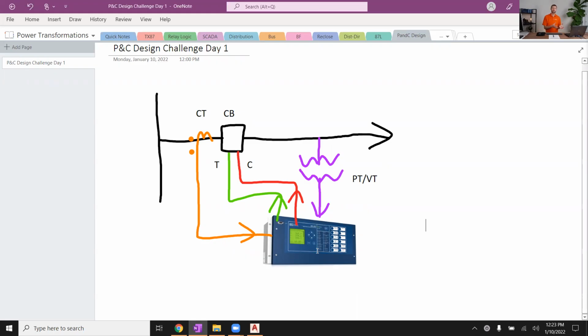Essentially, it's a computer. Nowadays, it's a microprocessor machine, and it's monitoring the power system from the voltages and or current signals and other input signals to detect anomalies, abnormal conditions, faults. And once it determines that a fault exists, it's going to take an action to automatically drive a response to clear that fault, to isolate the faulted section of the power system. That relay is going to command one or more circuit breakers to open, to trip. And then once that is open circuited, the faulted section of the power grid is de-energized, is in an outage condition, and it's been protected from further damage at that point, protected from damage to human life and perhaps a risk of fire or explosion, et cetera, from fault current conditions.